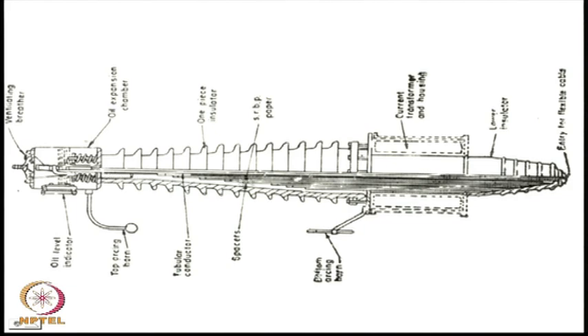These are normally oil filled with an expansion chamber on the top and also provided with arcing horns, so that if there is a flashover, it occurs between these arcing horns. It is also provided with a current transformer which measures the current flowing through the terminal. These protrusions of the porcelain cylinders provide for extended insulation and protect against corona.